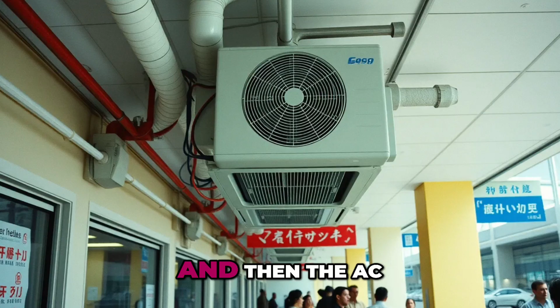The cooling calculation is a bit more tricky, because you've got your internal heat gains—your equipment, your lights, your computers, etc. You've then got people, who have both a sensible and a latent heat gain component. And then you've got the facade, so you've got particularly solar heat gain on fenestration and glazing, which contributes to the heat load into a space.